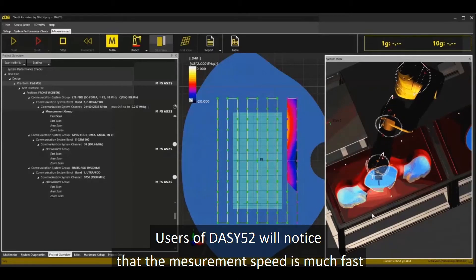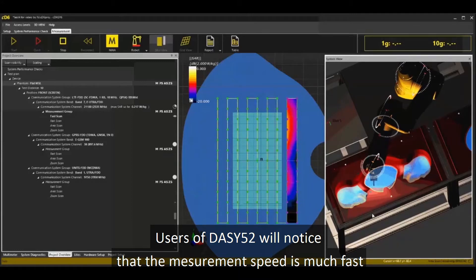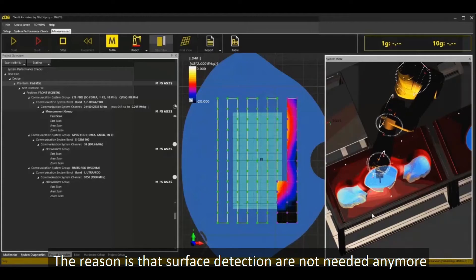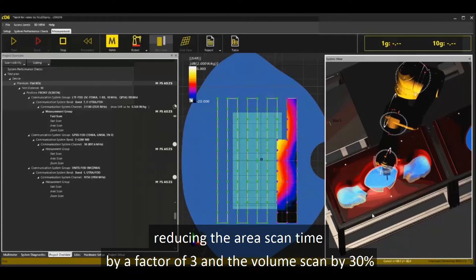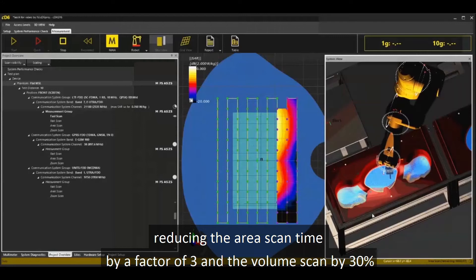Users of DASY52 will notice that the measurement speed is much faster. The reason is that surface detection is not needed anymore, reducing the area scan time by a factor of 3 and the volume scan by 30%.